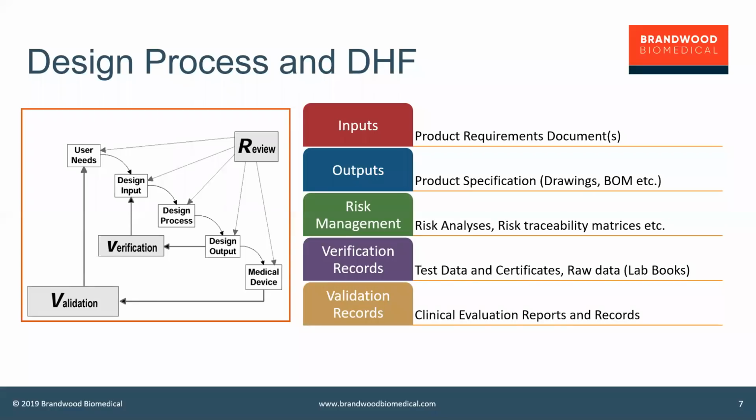Lastly, we have the validation records. Again, remember, validation is to prove that the product meets the intended need of the end user. So these are the real use scenarios and the real testing of clinical use and the clinical trial design and all of those evaluation reports and records that are related to the use of the device as it's to be used by the end user.